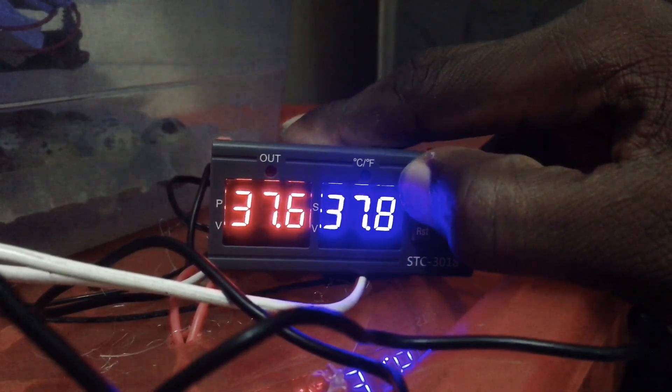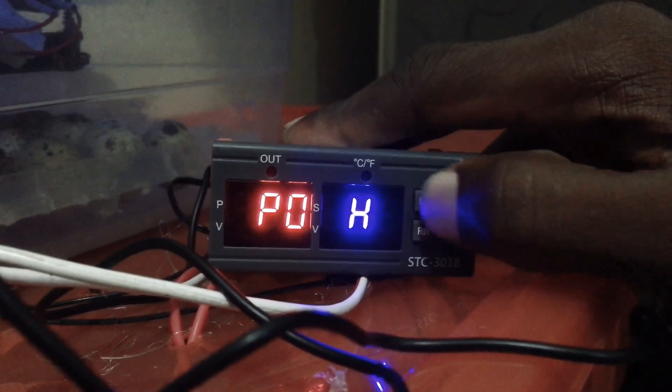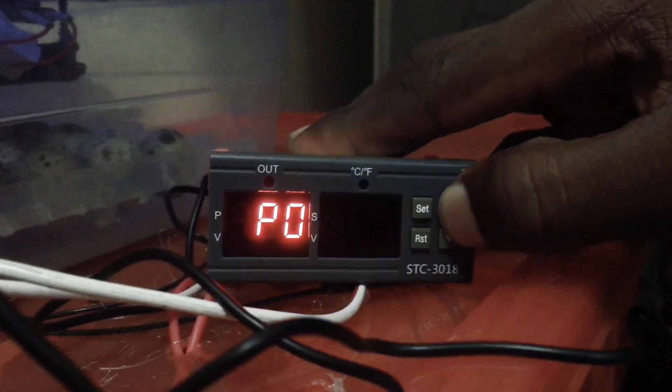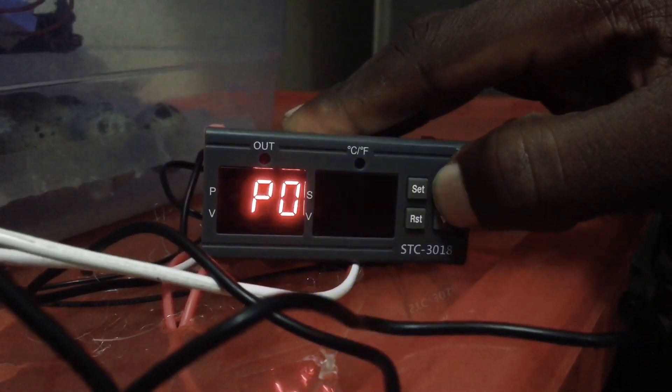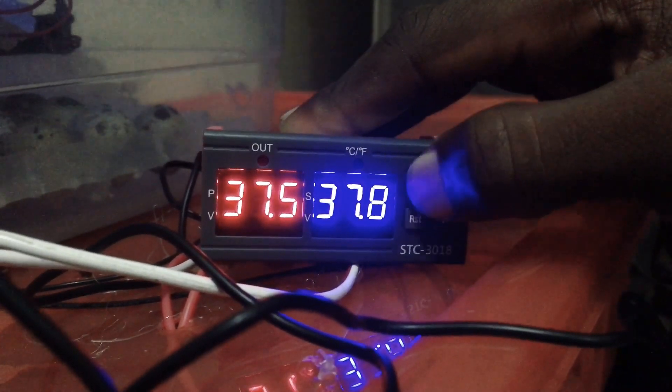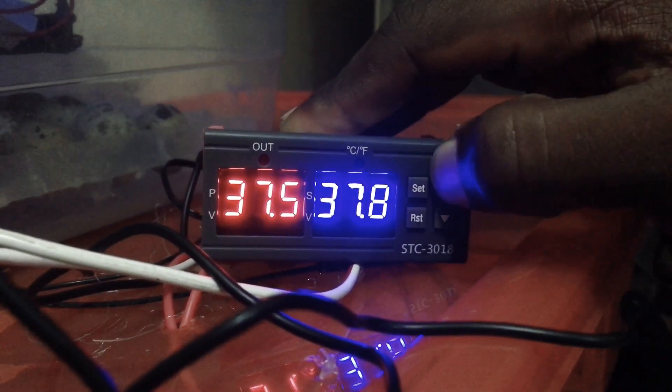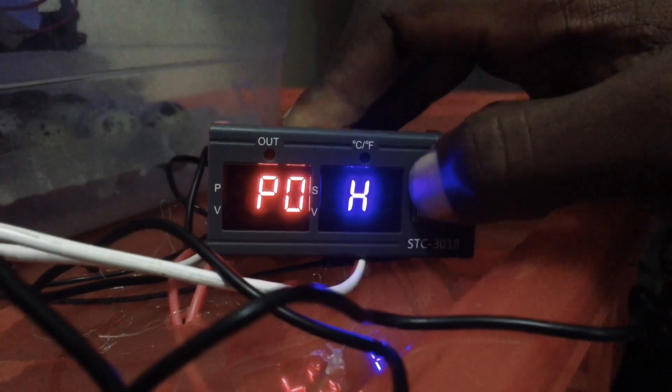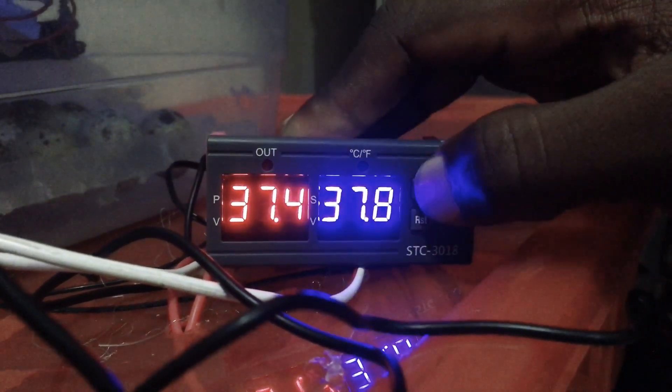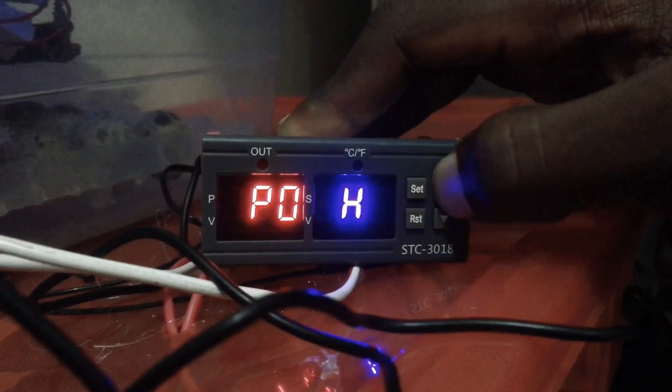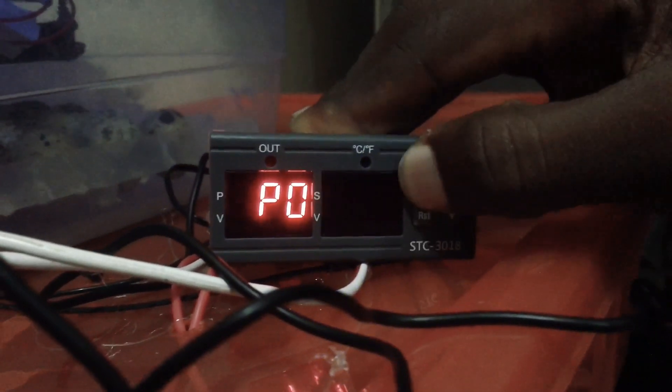The blue side should be on H - that's heat or hot. It shouldn't be on C because it's an incubator, it should always be on H. So we press and hold, P0 shows up. You press again, and press again. You set it to H.